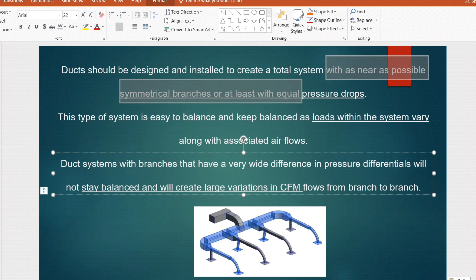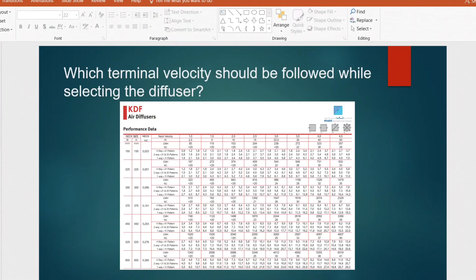The next question is: which terminal velocity should be followed when selecting the diffuser? For example, here is a catalog for a square four-way diffuser showing different throw distances — 0.9 m, 1.2 m, 1.8 m — at different terminal velocities. The question is: which terminal velocity should I follow?